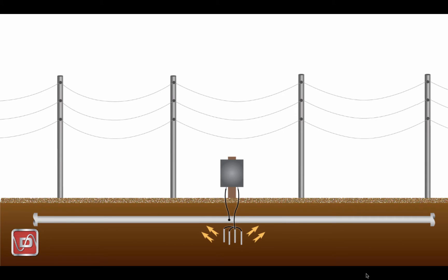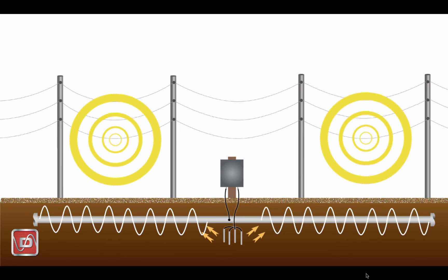Many pipelines are located in rights-of-way with overhead power lines, creating induced AC voltage effects. This is where our AC mitigation projects come in. Mitigating the induced AC is important both for personal safety issues and to prevent AC corrosion issues. There are many standards that require mitigation of these induced voltages to certain safe levels, so we have to address these effects. Pipeline owners also have to address other temporary overvoltage conditions such as AC fault events and lightning strikes.